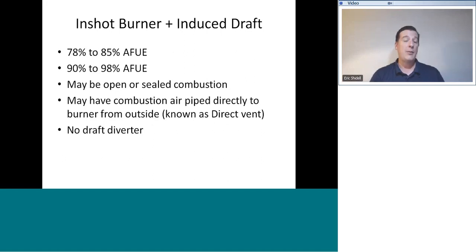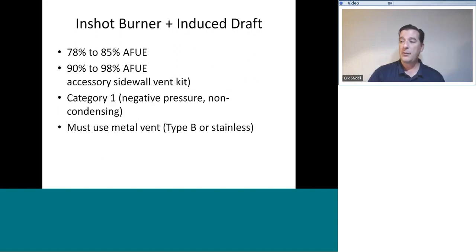It wasn't very common, but there were some sealed combustion, outdoor combustion air only 80% furnaces made over the years. That's known as direct vent, by the way. When combustion air is drawn directly from outdoors through a dedicated combustion air intake pipe, and then the vent goes directly to outdoors, that's called direct vent. There is no draft diverter.